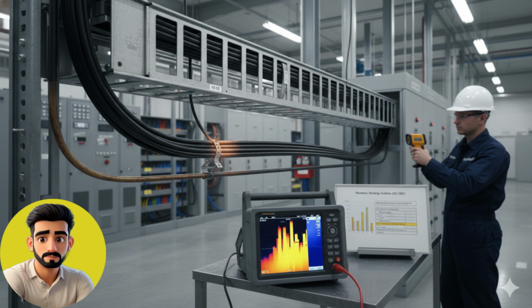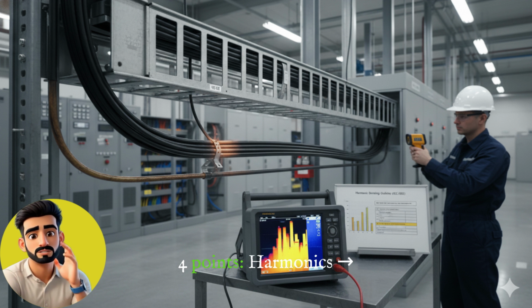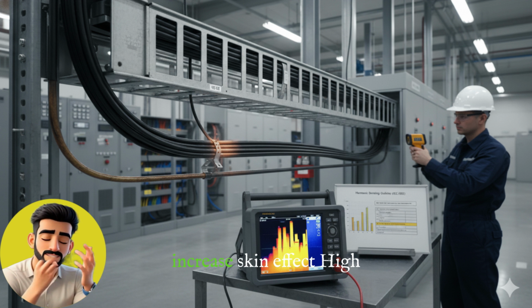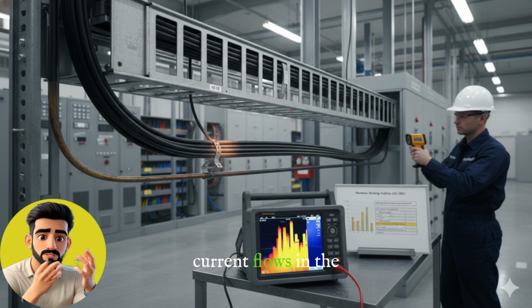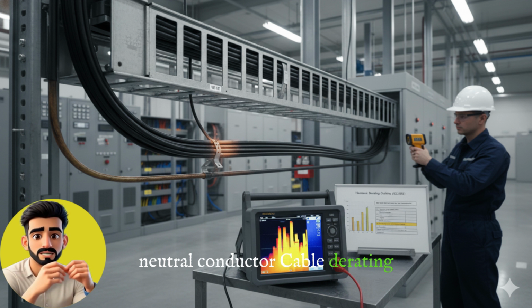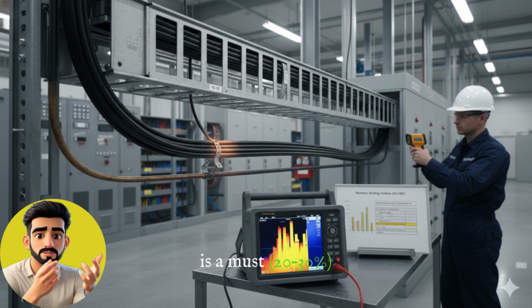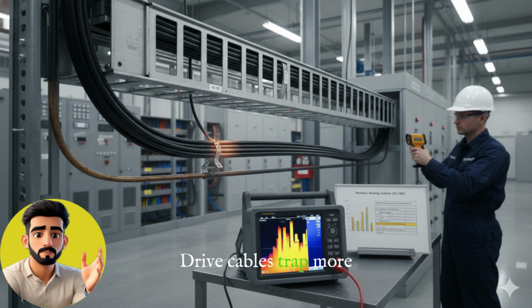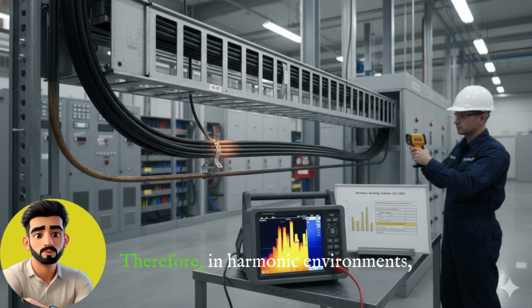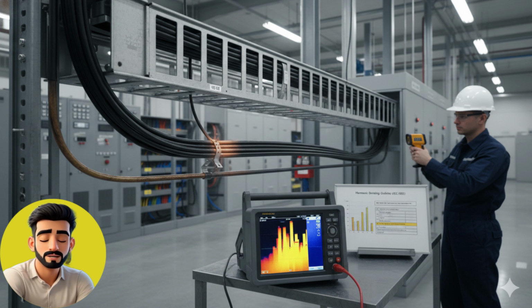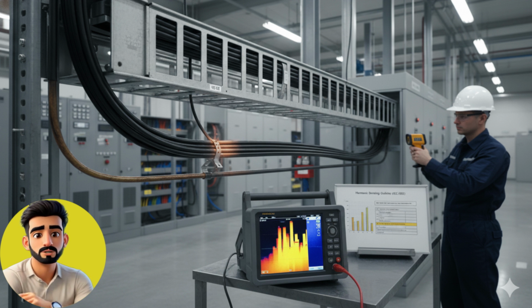the motor load. 6. Summary: cables and harmonics. Always remember these 4 points. Harmonics increase skin effect. High current flows in the neutral conductor. Cable derating is a must, 20 to 30%. Drive cables trap more heat in the tray. Therefore, in harmonic environments, cable selection, sizing, grouping, and derating are extremely critical.